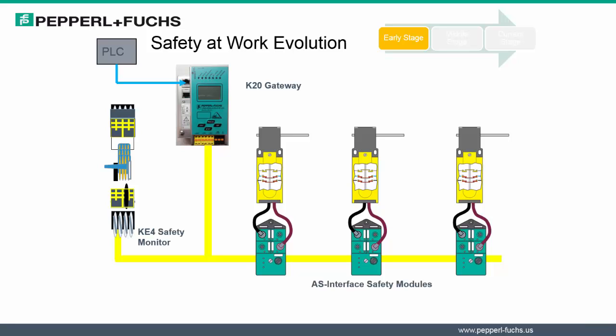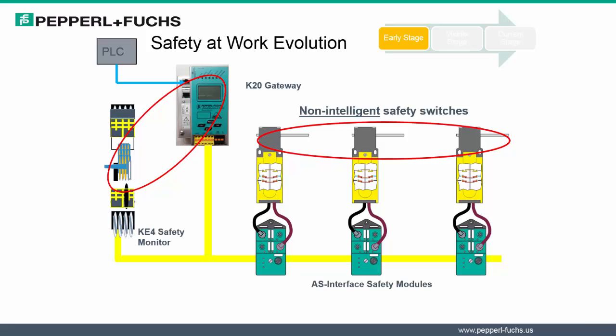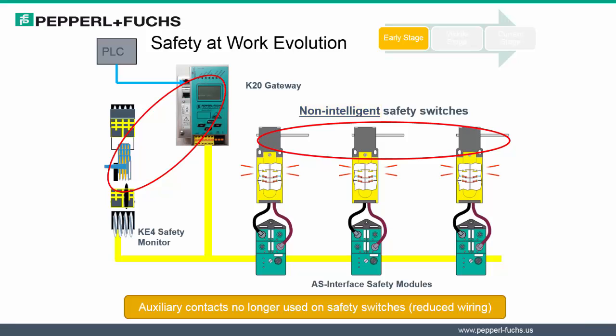Let's begin with the early stage of the evolution. AS Interface Safety at Work is a system that enables networking of safety devices, safety door switches, e-stops, and other safety devices using standard AS Interface networks. In the early stages, the AS Interface gateway was separated from the safety monitor. However, the safety monitor took the place of a safety relay in conventional hardwired systems. Since the devices connecting to the modules were unintelligent, the actual modules were addressed, not the devices. One last observation is that auxiliary contacts were no longer used as with traditional safety devices, which further reduced some of the wiring required.